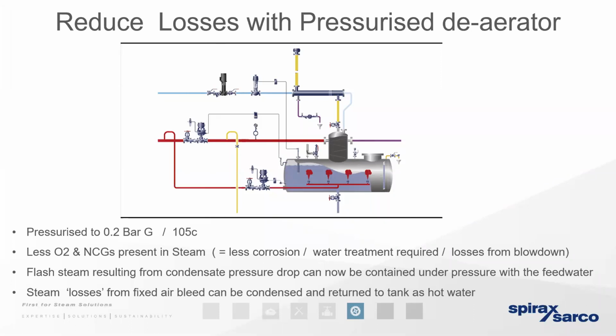That's really because a small mass of condensate is always going to be lost in the flash steam. But by minimizing those losses, we can certainly move towards that net zero loss system. I mention moving towards it rather than achieving it, because we are still going to experience a very, very small amount of energy loss or mass loss as a result of performing that essential blowdown that we've spoken about.